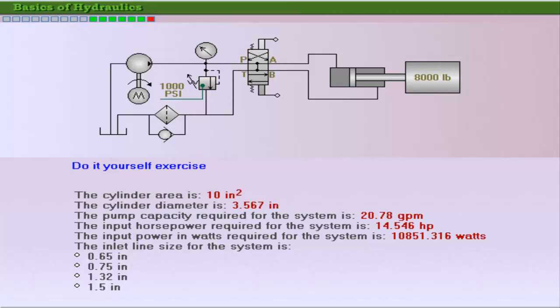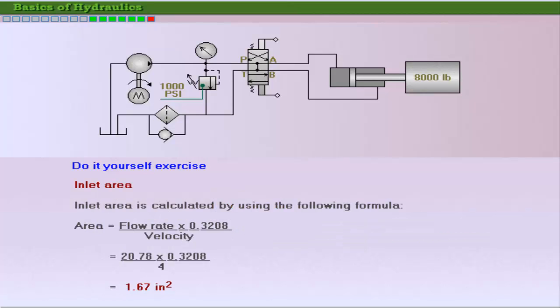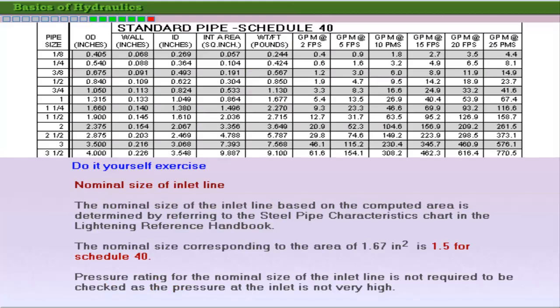The area of the inlet line is calculated in order to determine its nominal size. Refer to the steel pipe characteristics chart in the Lightning Reference Handbook to determine the nominal size of the inlet line. The nominal size for the inlet line corresponding to the computed area of 1.67 square inches is 1.5 for schedule 40.